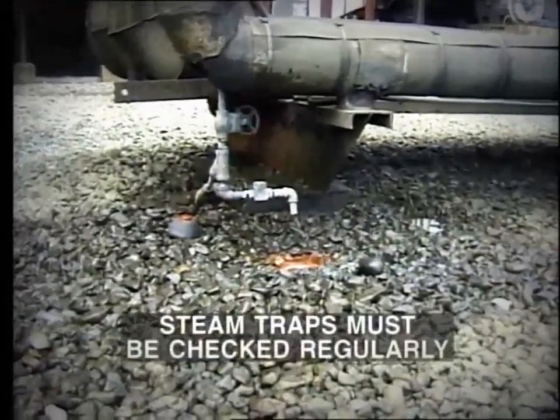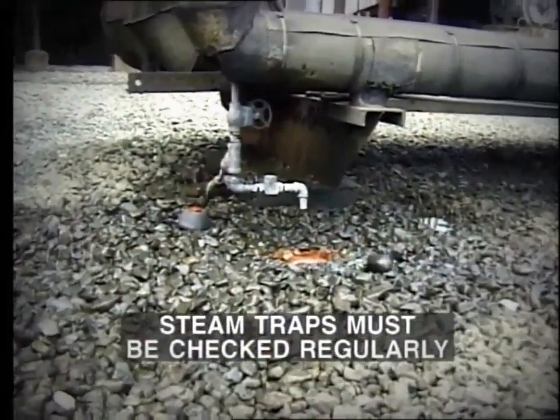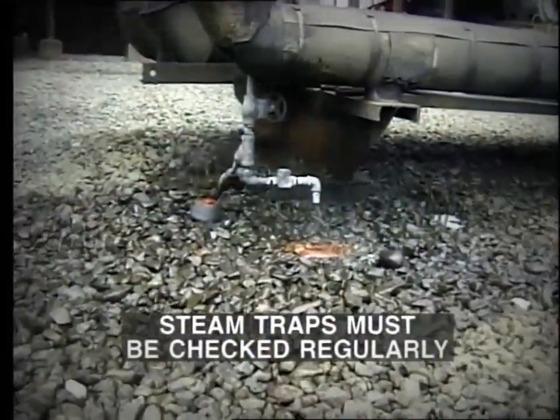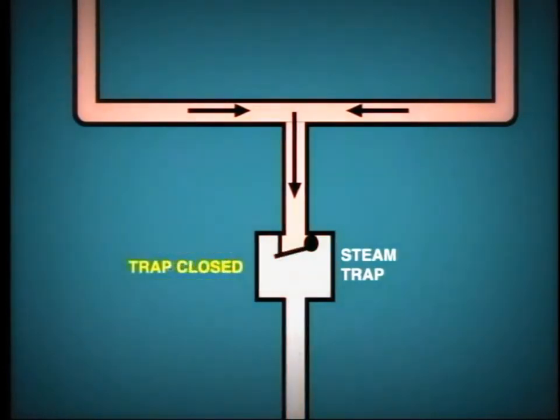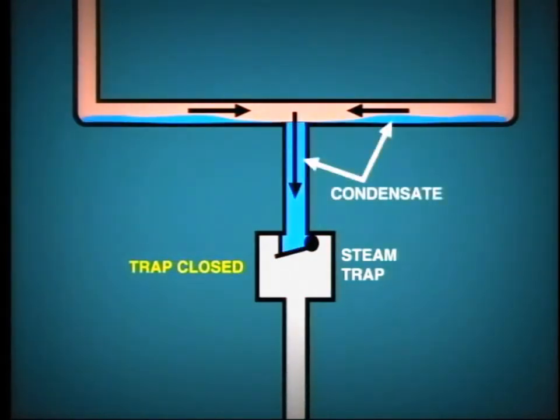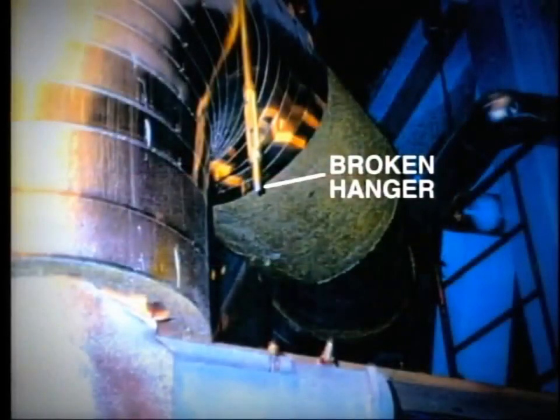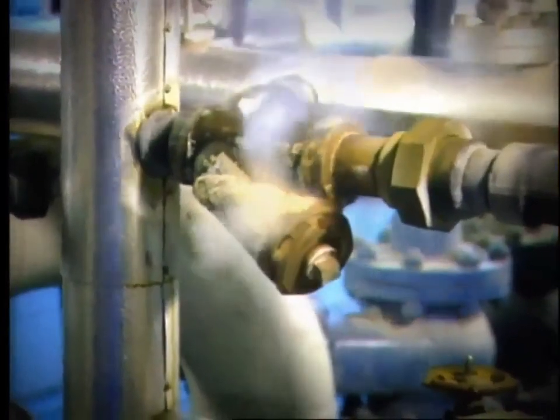The operator should regularly check that the steam traps are functioning correctly, that is, to discharge condensate in regular bursts. If the steam trap is not sealing properly, it will pass steam continuously and so be a source of considerable waste. Conversely, if the trap remains closed, then condensate will accumulate inside the auxiliary steam piping. In this case, we will probably be made aware of the problem by water hammer in the pipework. This occurs as the water flashes into steam intermittently. The water hammer can produce considerable mechanical movement and shock to the steam pipework and may result in broken hangers and supports, as well as leaks at valves and other equipment connections.